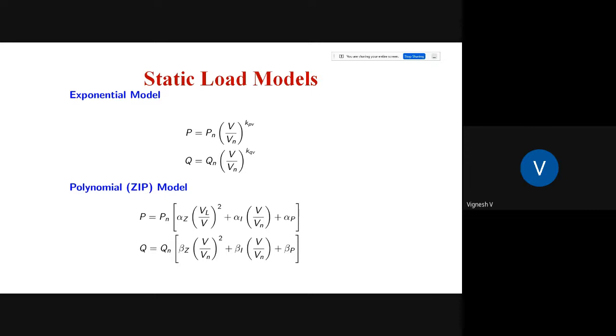So we'll talk about some of the standard load models that people use. We use exponential based load models, and we use the ZIP model. We are all aware of that. In an exponential model, KPV and KQV are the parameters that we need to find out. And in case of the ZIP model, alpha Z, alpha I, and alpha P, the coefficients of constant impedance, constant current, and constant power, are the parameters that we would like to estimate. So these are all static load models. The equations that relate the power and voltage and frequency are all algebraic functions, right? Because we are not modeling dynamics here. We go to the next type.